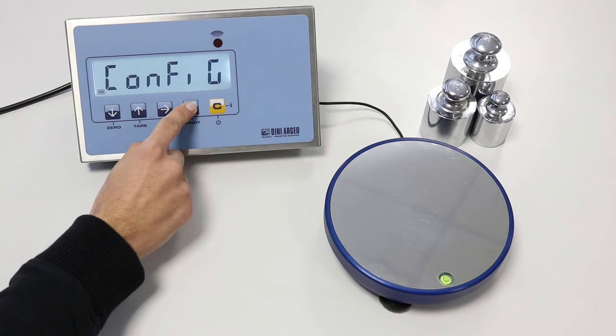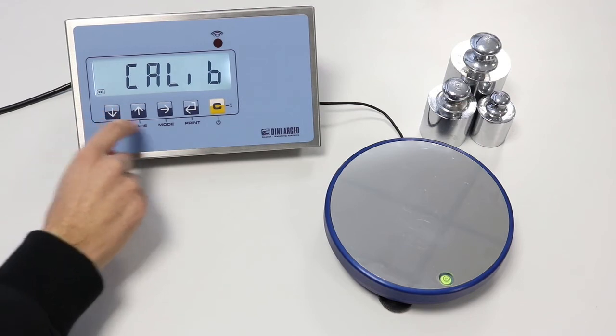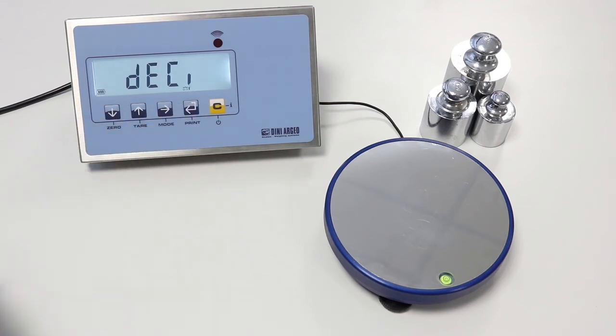Enter the config parameter by pressing PRINT. Scroll down until CALIB and press PRINT. Now we set all the metrical parameters.